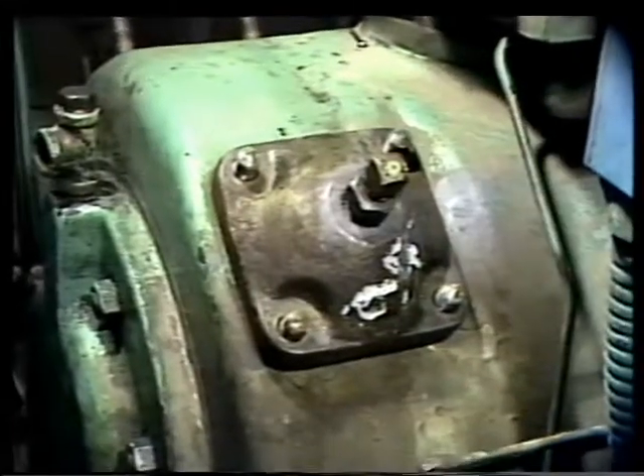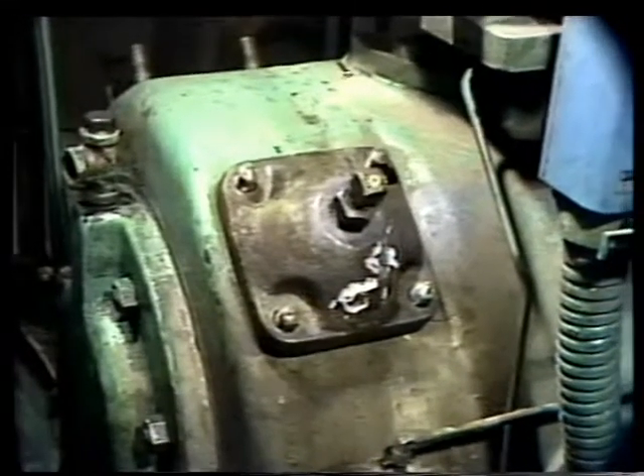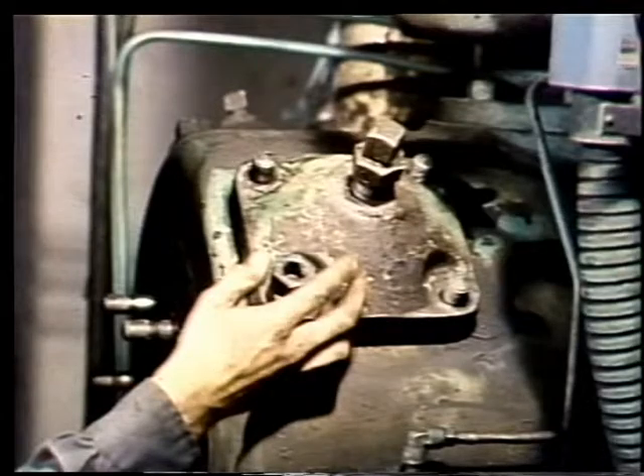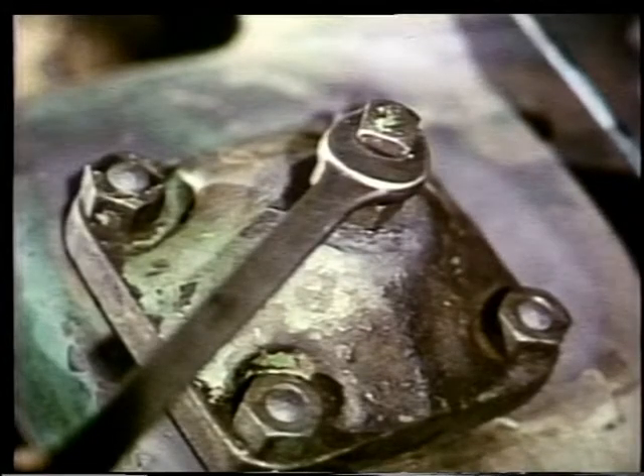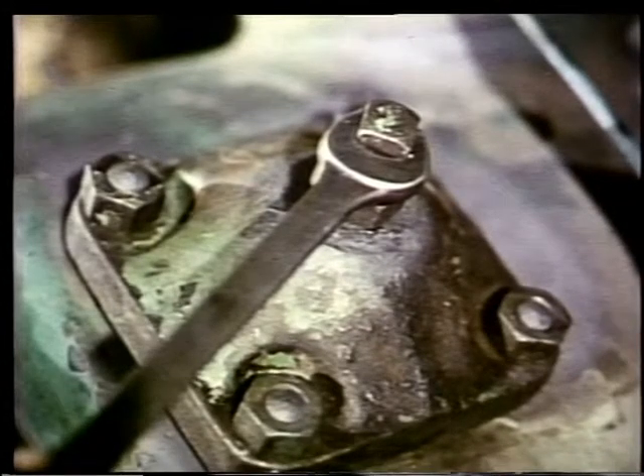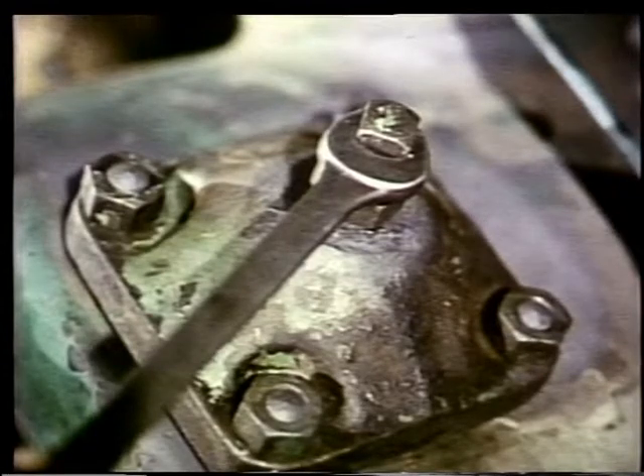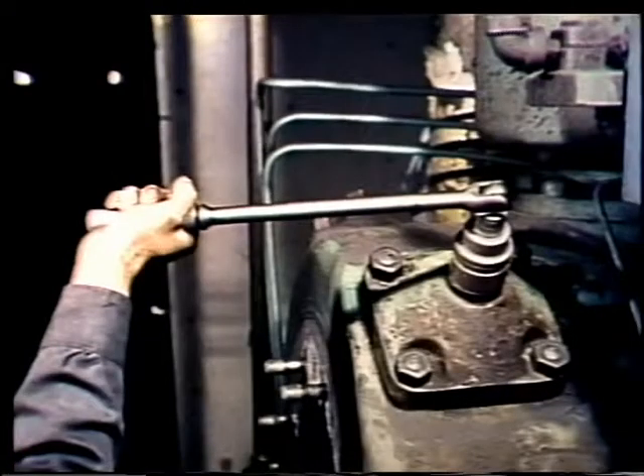Now that the valve is in the cylinder, you can replace the outer cap on the casing and bolt it in place. Next, tighten the bolt, which is threaded through the outer cover. This bolt presses on the inner cover and holds the valve in place. The last step is to tighten the nut. This prevents air from leaking out around the bolt.